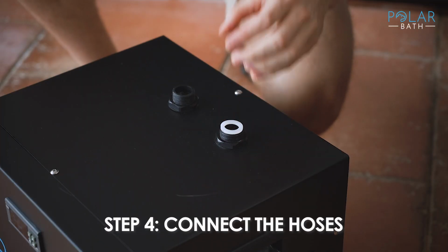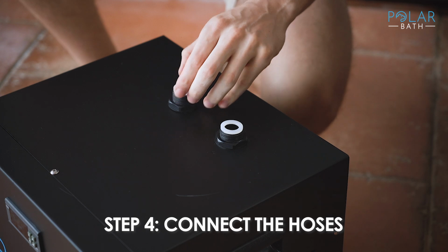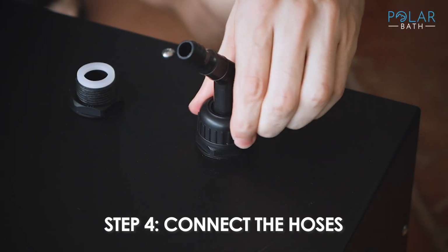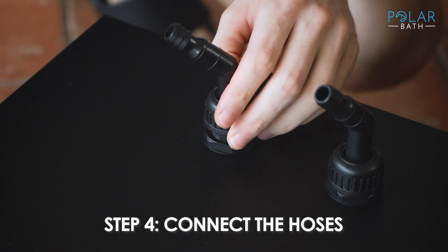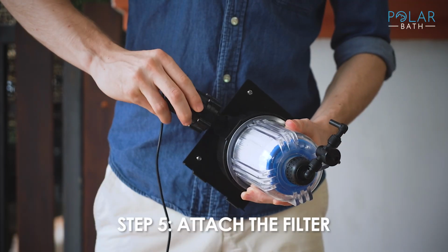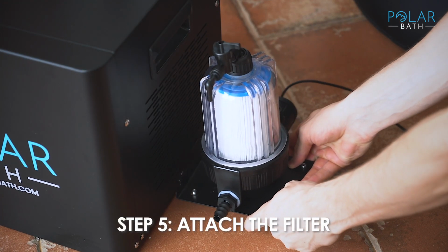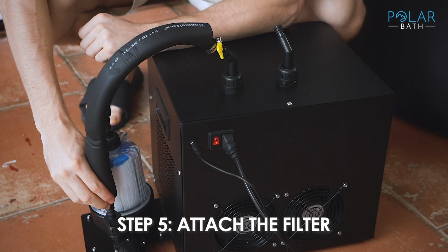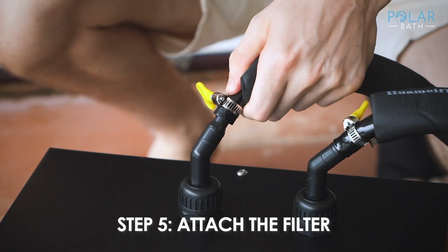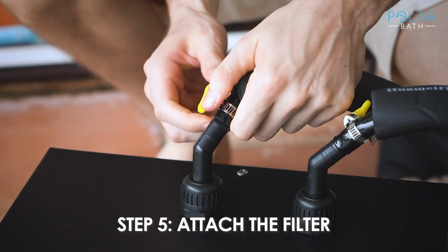Now, attach the hose connectors to the chiller inlets and outlets. Remember to place the white rubber rings on the outlets first. Secure everything tightly. Connect the short hose to the pump adapter and slide the insulation piece onto it. Attach the other end to one of the chiller connectors, and then connect the long hoses to the water filter and the other chiller outlet.